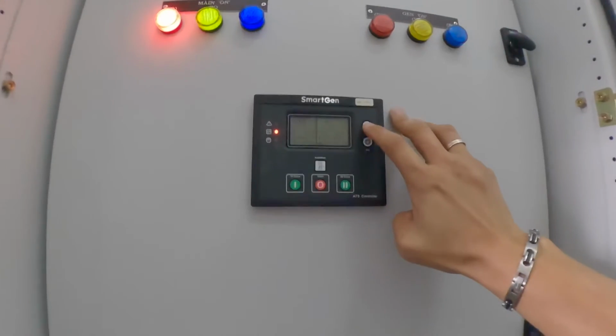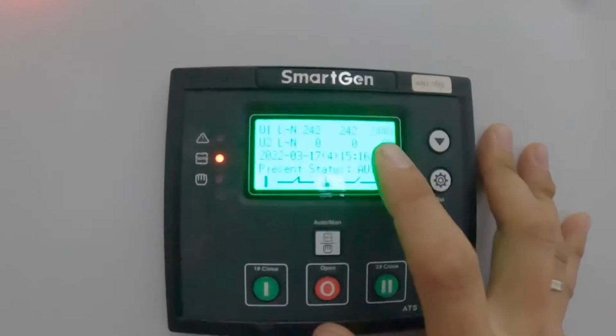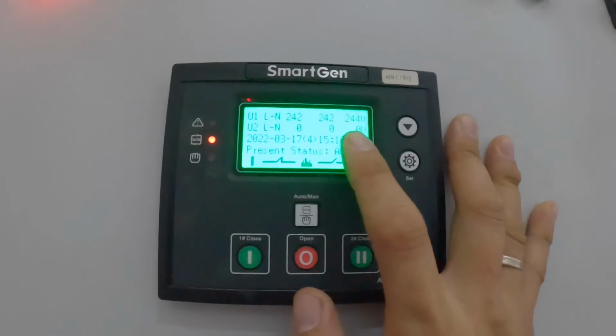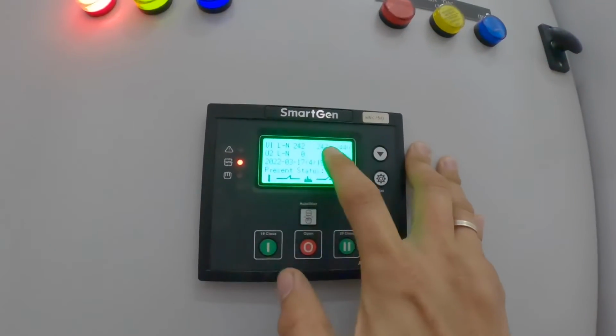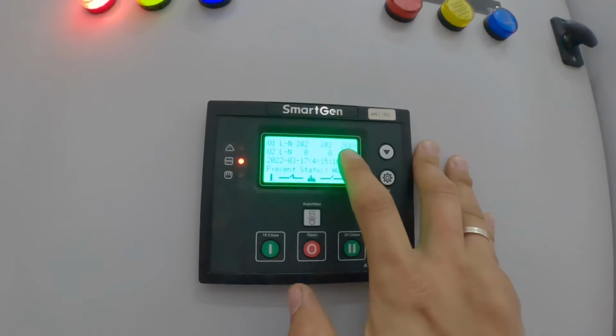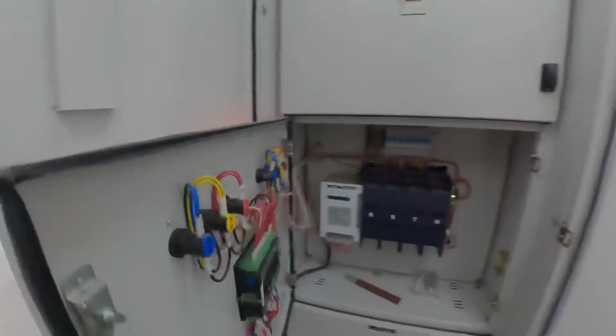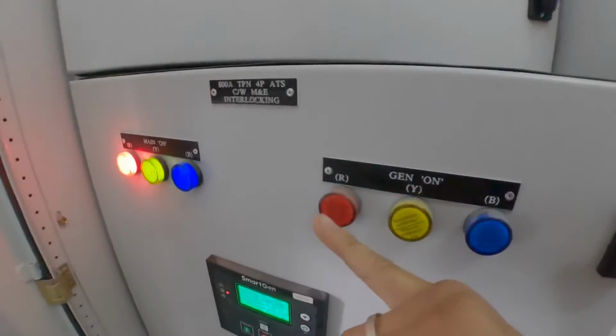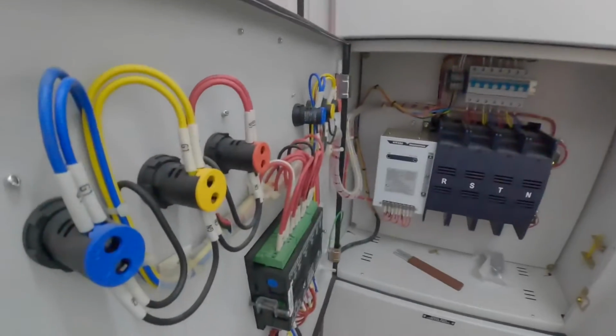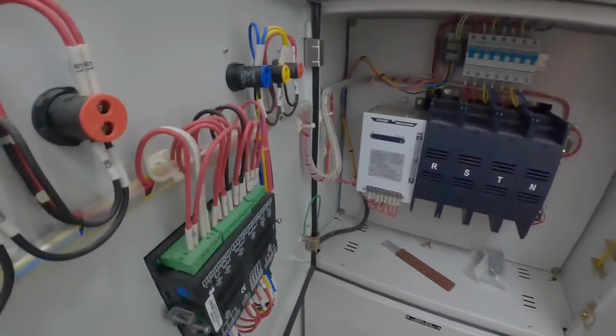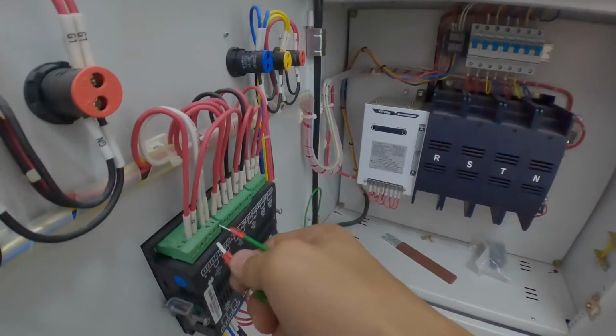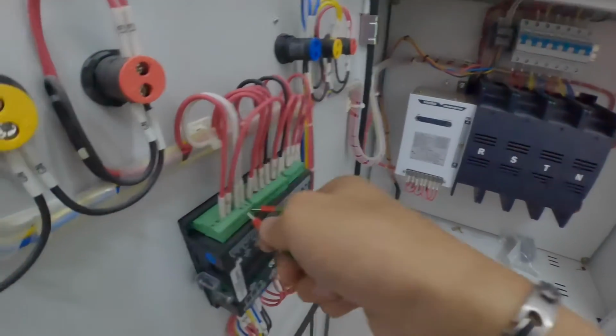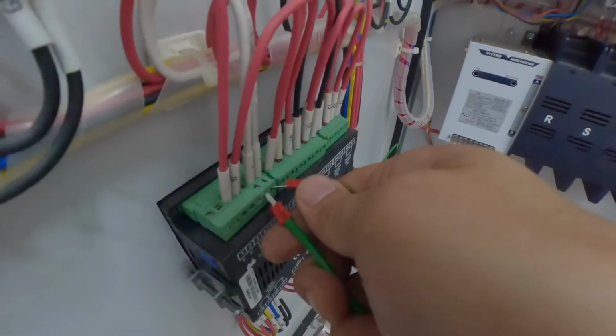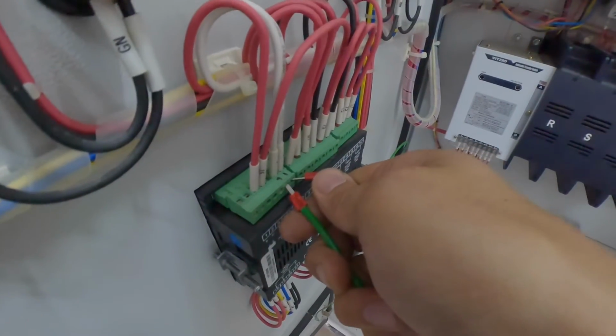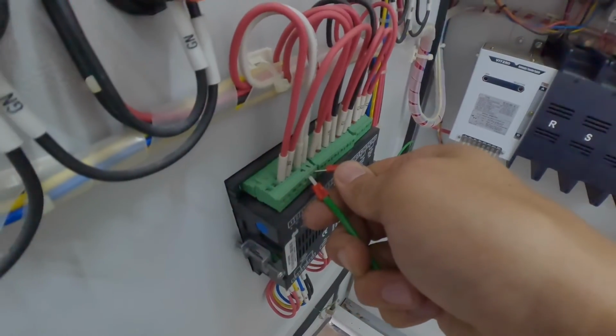As the genset is running, I will be able to see the genset voltage over here. This is the main supply voltage reading 242, 242 and 244. Let's get started. When the genset is running, this indicator light will be on. I'm going to jump the signal to allow the genset to start automatically and remotely through here. Currently the genset is under auto mode.